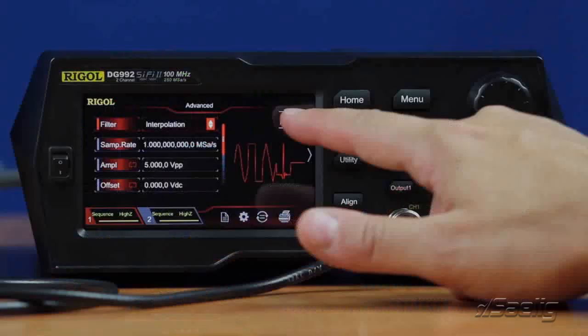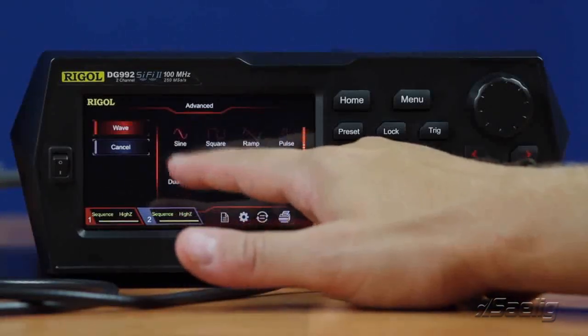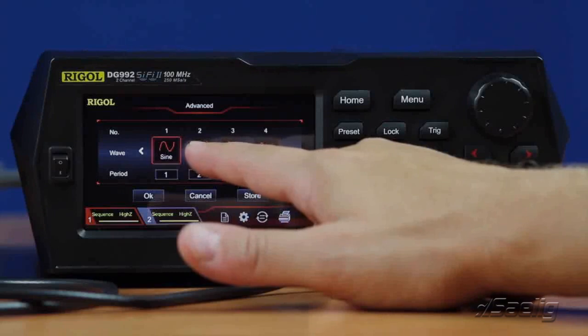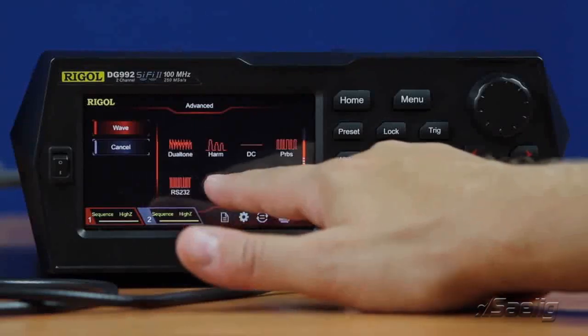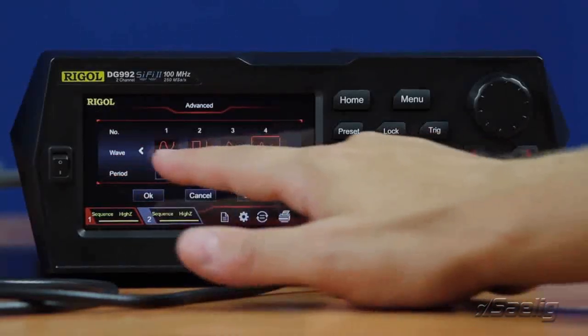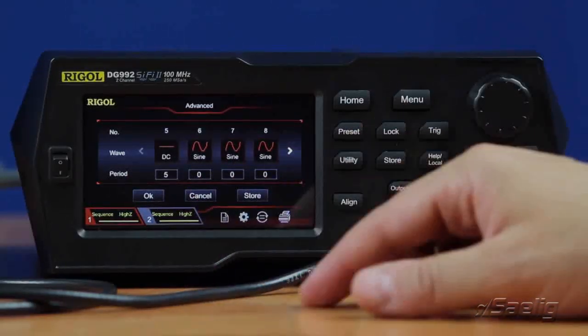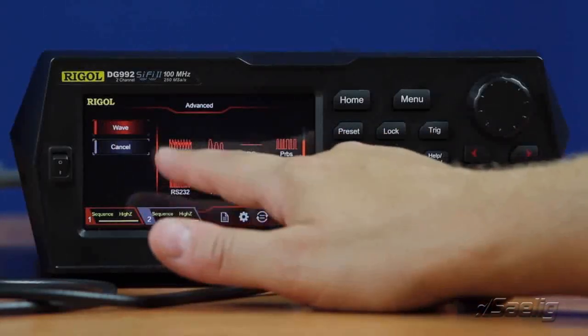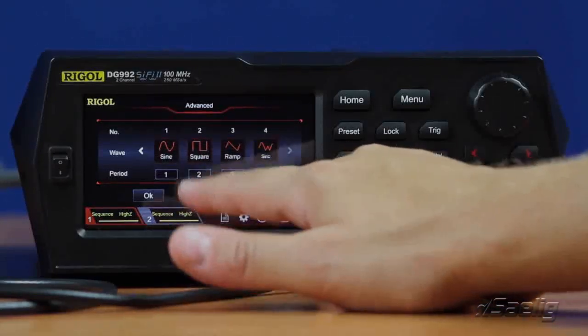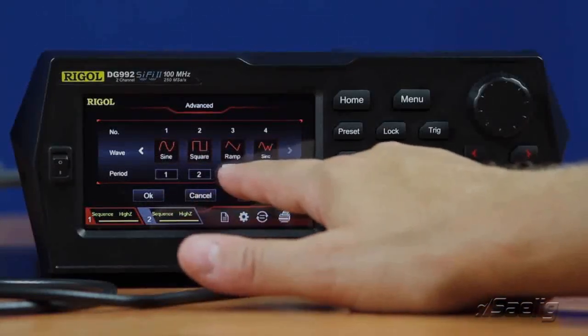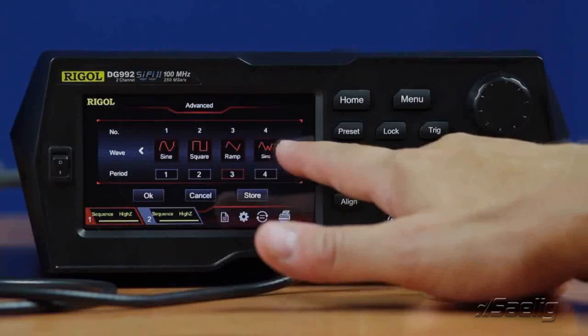Let's see how it works. We can go in and set both a signal type from either our standard signals and a period, or more complex signals like arbitrary waves. Here we'll select an arbitrary wave and a sinc function. We can also select DC levels or other signal types between these. Let's set a waveform with one sinusoidal period, two square wave periods, three ramp periods, four sinc arbitrary sinc function periods, and then a DC level between.